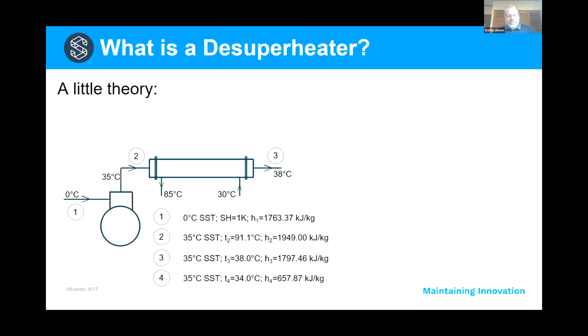Now, first of all, I might dwell a little bit on what a desuperheater is. So this little diagram here, that round thing with a top hat is a compressor, and the other rectangular thing there is a desuperheater. I've shown this as a shell and tube. It doesn't have to be that way. The numbers 1, 2, 3, 4, you see later, they are representative of the condition of the refrigerant. So inlet condition to the compressor is number 1. Saturated suction temperature, you can see here, 0 degrees.